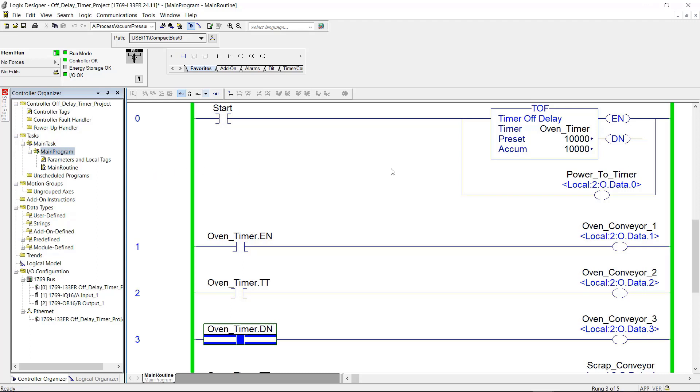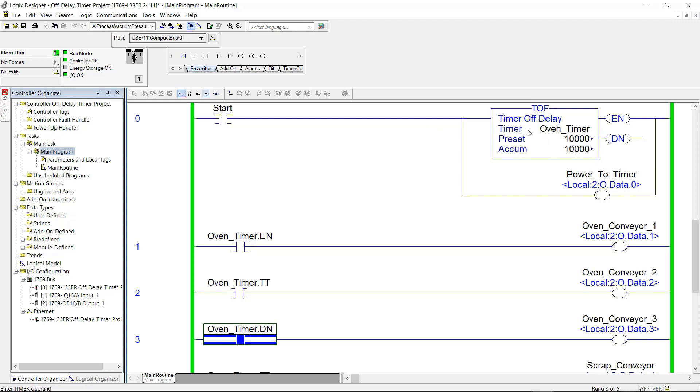And I have my power rails here. The run mode is green. The controller and the IO are green and they're all okay. Now if you look at the timer right now, the timer preset equals the accumulated value of 10,000.